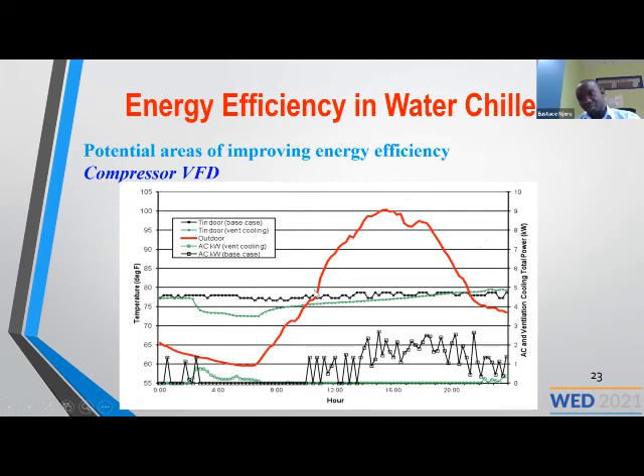You can see here, measured during an energy audit, the green part showing the power demand. The power demand is supposed to vary as the temperature varies. The black part shows the kilowatts, and you can see that as the temperature increases, this one increases. So this is an ideal case, a good automated case. In other cases, you find that the power demand is constant, even if the temperatures are low or high. In that case, during the low temperatures, you are wasting a lot of energy.